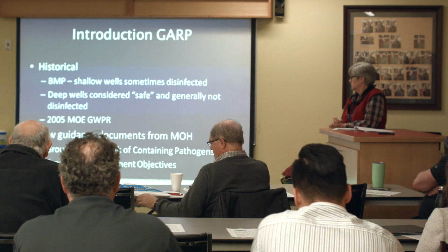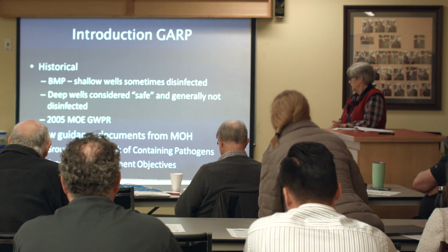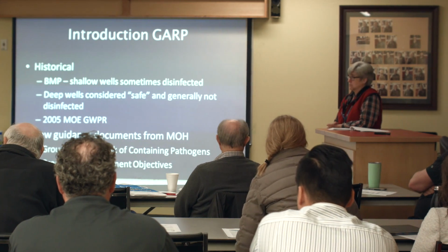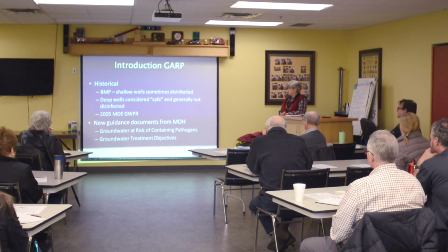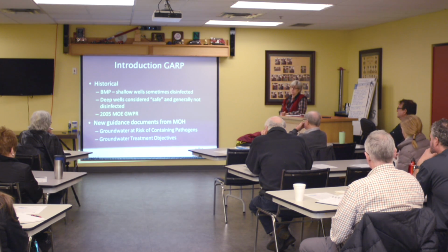In 2005, the Ministry of Environment came out with the groundwater protection regulations, and that included standards on well construction, making sure you've got a surface seal, making sure you have a cap on it, registering it with the Ministry of Environment. From the Ministry of Health, we've had our new guidance documents coming out, and the ones that we're going to talk mostly about today are groundwater at risk of containing pathogens, or GARP, and the groundwater treatment objectives.